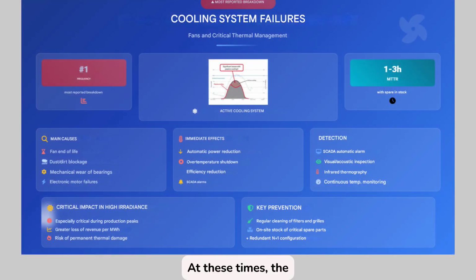At these times, the system enters thermal limitation mode or even shuts down, resulting in a direct loss of revenue and the risk of permanent damage to internal components such as IGBTs or capacitors. From an operational perspective, these failures result in automatic power reduction, triggered SCADA alarms, and, in extreme cases, shutdowns due to overtemperature. To detect them early, the most effective approach is a combination of continuous temperature monitoring, infrared thermography, and periodic visual inspections. SCADA alarms also help, but they are no substitute for a well-planned preventive inspection.